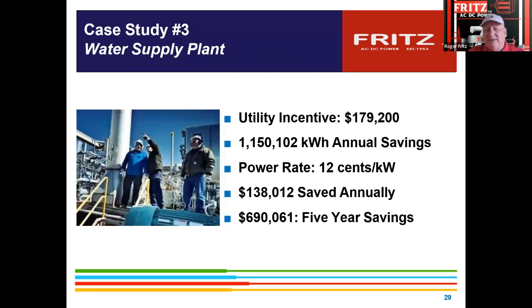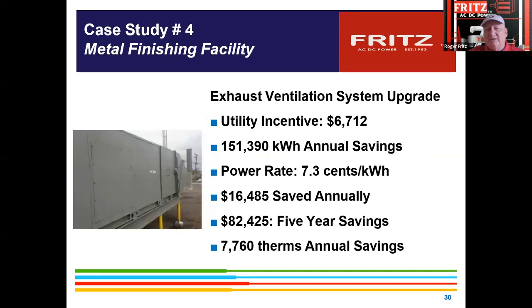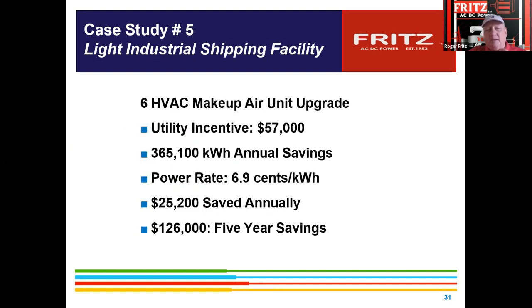So they didn't go over, or this would be a water supply facility, where we put drives on several of the lift pumps, several of the booster stations. Again, they had some throttling going on, and then it was just balancing, again, the frequency, voltage, and power to the demand of the facility. And the nice thing about controls today is they have a lot of unique software in them, so you can actually pre-program those properly to run in those applications. Exhaust fans, ventilation upgrades, makeup air, again, upgrading those. And these happen to be in some Midwest locations where the utility rate was much cheaper than some of the coastal locations.